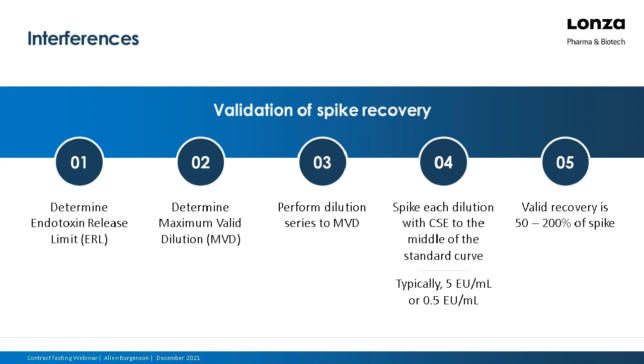You're looking for interferences. Now, they could be inhibition, where you're not recovering your spike, or enhancement, where there are times when the apparent endotoxin content is elevated due to enhancement and from things like beta-glucans. It's determined by judging the recovery of a known endotoxin spike, a positive product control, or PPC. And you again dilute all the way out to your MVD, spike your PPC in the middle of the standard curve for those dilutions. But there is a special procedure for the gel clot that we won't get into. And the specification of PPC recovery is 50 to 200%.